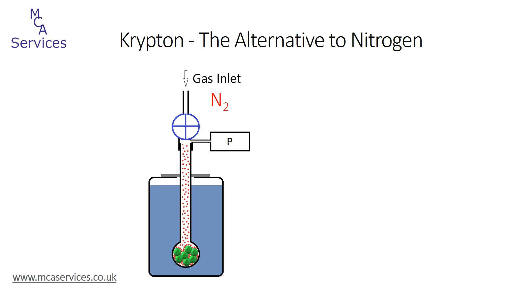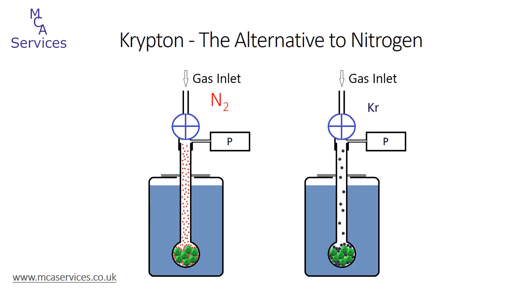But there is an alternative. The number of adsorbate atoms or molecules present in the free space of the analysis tube at any relative pressure is dictated in part by the saturation vapor pressure of the adsorbate. For nitrogen this is a little above atmospheric pressure — let's assume 760 millimeters of mercury. Krypton, on the other hand, has a very low saturation vapor pressure, typically 2.3 millimeters of mercury. The consequence is that at any given relative pressure there will be about 330 times fewer krypton atoms in the free space than there would be for nitrogen molecules, for the same degree of surface coverage. Ultimately this means that with krypton, the number of atoms adsorbed on the surface is much larger relative to the number in the free space, and the isotherm becomes much more reliable for the calculation of BET surface area.